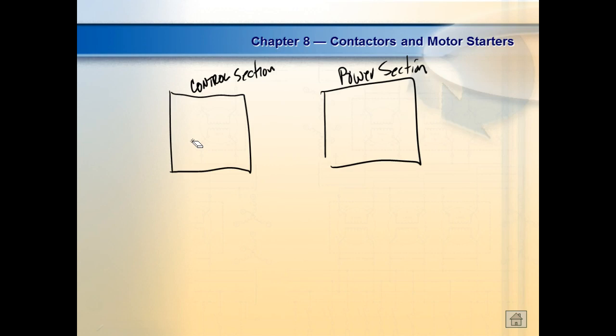You understand that? Then I get over to the power section. These relays are going to be a lot bigger. Why? Because the contacts have to be a lot bigger because they're controlling a lot more power, right? But they're going to be doing it at a higher voltage. So when we talk about control relays, which we're going to start out using, all your control relay contacts are going to be up here. Your power section contacts are going to be over here. The relays will be over there, but their contacts will be over here. Y'all understand that? Yes, sir.